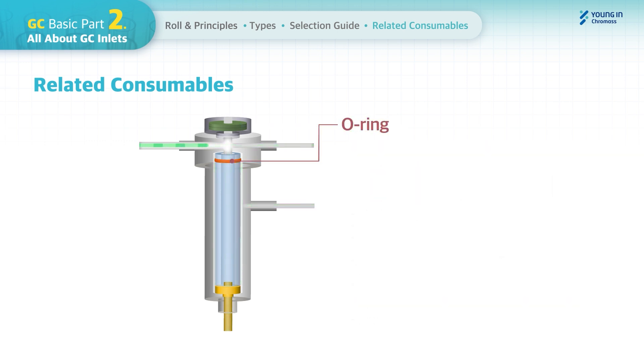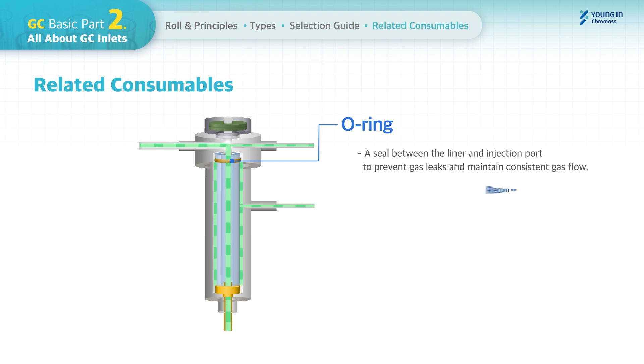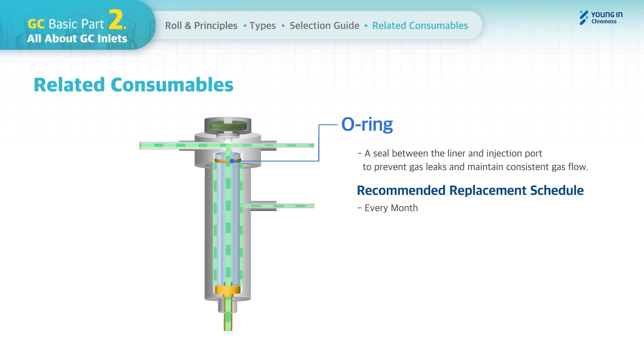An inlet O-ring seals between the liner and the injection port of the GC, preventing gas leaks and maintaining consistent gas flow. This needs to be replaced periodically before it gets damaged or worn out.